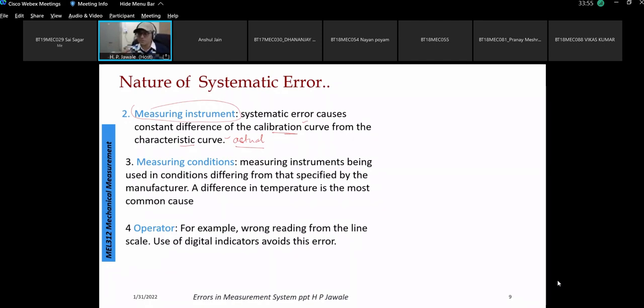So when we purchase any measurement system, we are given the attributes of the system, that our system is accurate up to a specified value, say plus minus some value, and then the characteristic curve is also shown, that this system is going to behave linearly up to this value of input, then a little deviation. Whatever the characteristic, this curve is specified by the manufacturer, that we call a calibration curve. That is to be established often by means of calibration. That is why frequent calibration is required. So the error causes a difference. There is always a difference between the ideal curve of performance and the actual curve.